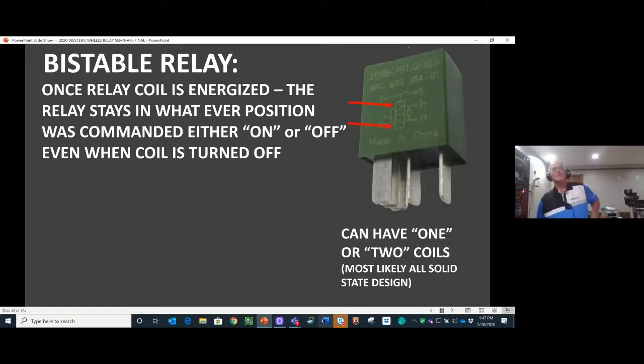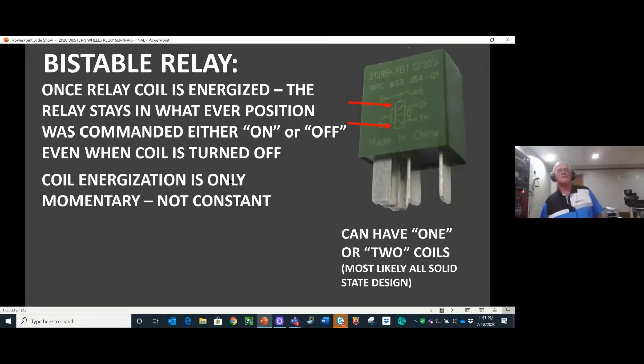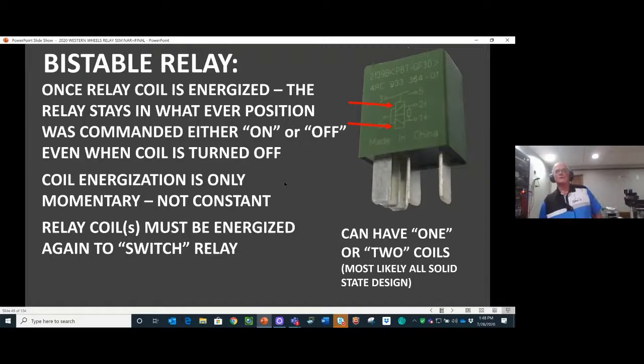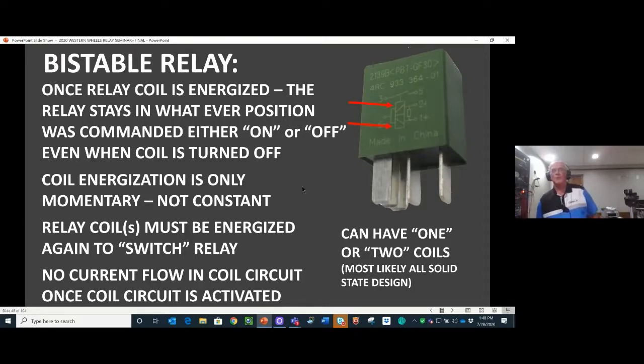The difference is once a bistable relay circuit is energized, the relay stays in whatever position it was commanded, on or off, even though the coil circuit is turned off. So the coil command is momentary and it shuts off, but the relay doesn't. The relay stays where it was told to be. In order to change the relay status, another circuit has to be energized to switch the relay back to its previous condition. There is no current flow in the coil circuit once that momentary circuit is activated.